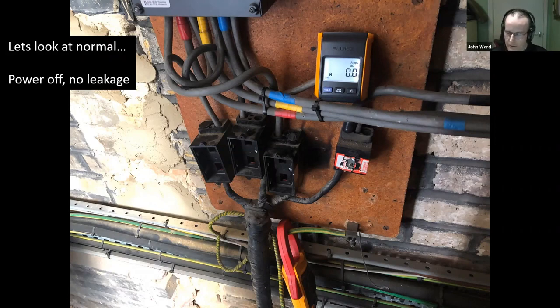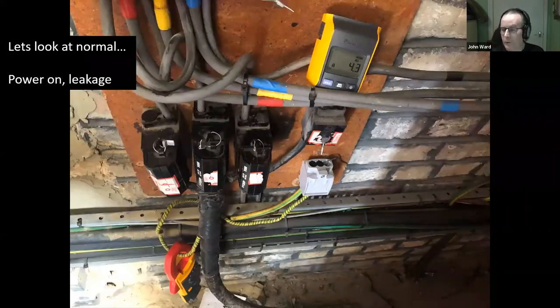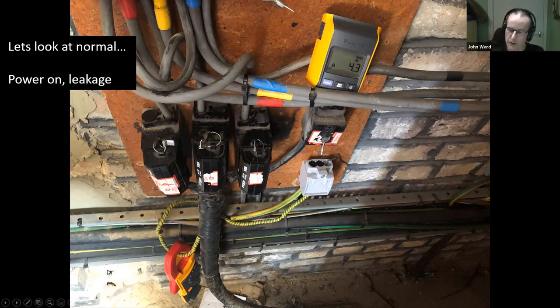Then we've got the same installation with the fuses in, clamp meter around there again, and we do have 4.3 amps of current there. Again, this is normal as well, because it's pretty much inevitable on installations that you're going to get some current on the earth conductor, depending on your installation. So fuses in, you get some current there; fuses out, it all disappears, goes to nothing.